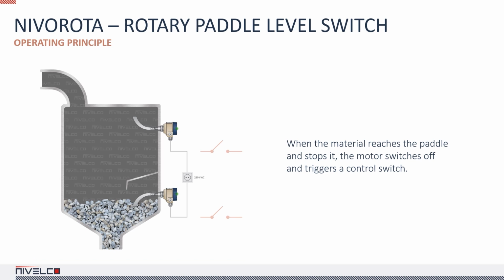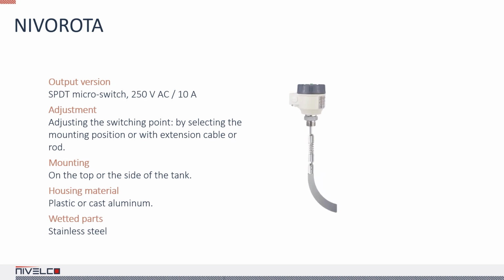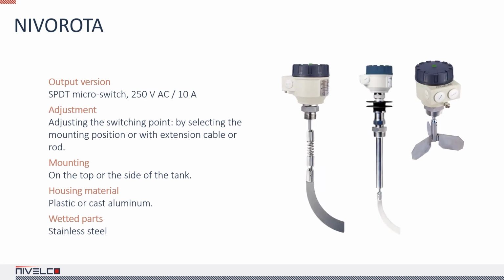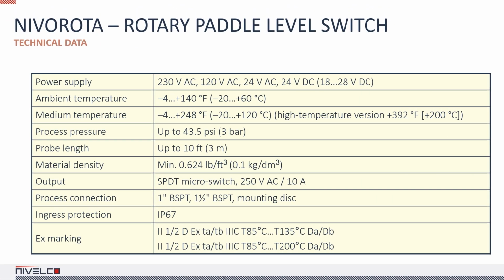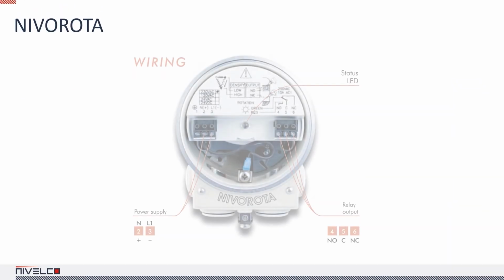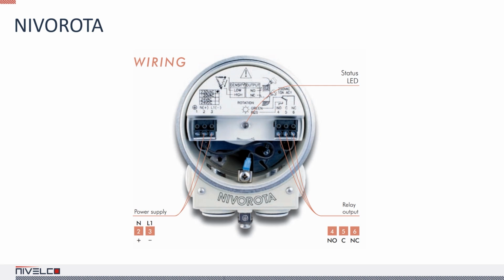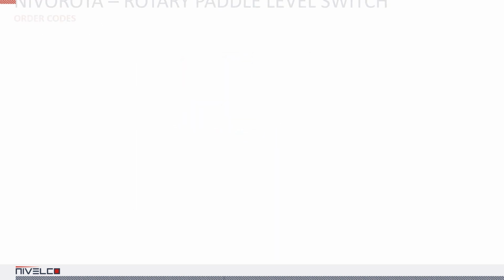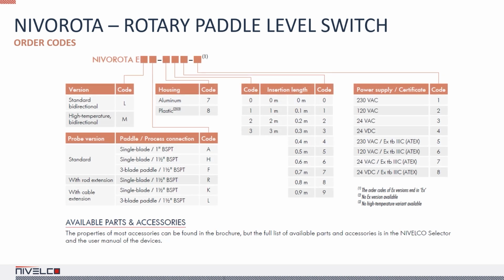The Nivorota E700 and E800 series provide all the advantages of the previous series in one unit. Thus, Ex versions are available for use in hazardous environments. The housing of the device is made of plastic or cast aluminum, and the wetted parts are made of stainless steel. The Nivorota can be used to detect the level of low-density powders and granular solids. They're simple to install, just like other similar Nivelco devices. There's plenty of accessories that make installing the device easier.